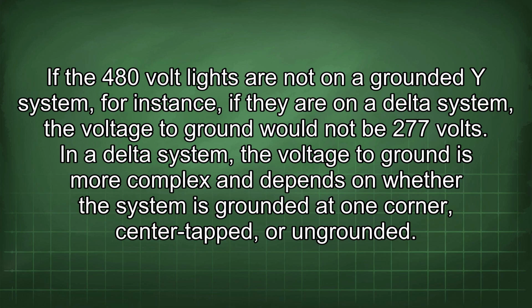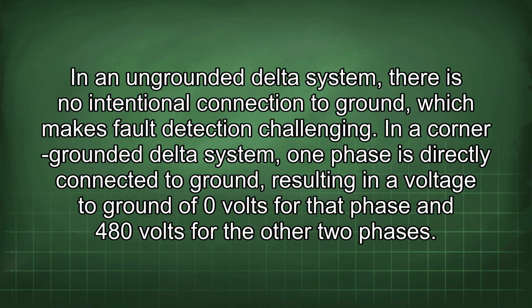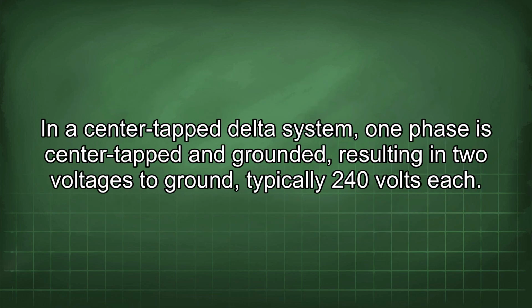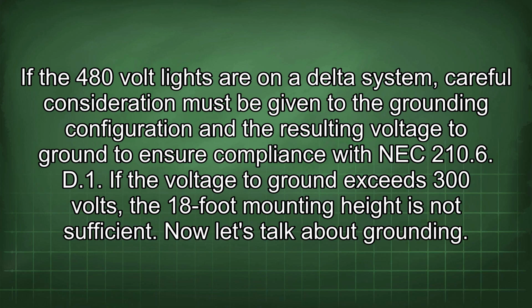If the 480-volt lights are not on a grounded Y system, for instance, if they are on a delta system, the voltage to ground would not be 277 volts. In a delta system, the voltage to ground is more complex and depends on whether the system is grounded at one corner, center tapped, or ungrounded. In an ungrounded delta system, there is no intentional connection to ground, which makes fault detection challenging. In a corner-grounded delta system, one phase is directly connected to ground, resulting in a voltage to ground of 0 volts for that phase and 480 volts for the other two phases. In a center-tapped delta system, one phase is center-tapped and grounded, resulting in two voltages to ground, typically 240 volts each. If the 480-volt lights are on a delta system, careful consideration must be given to the grounding configuration and the resulting voltage to ground to ensure compliance with NEC 210.6(D)(1). If the voltage to ground exceeds 300 volts, the 18-foot mounting height is not sufficient.